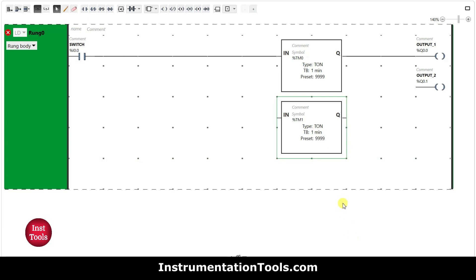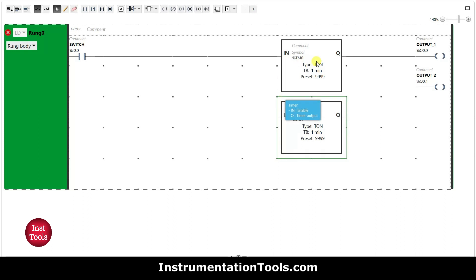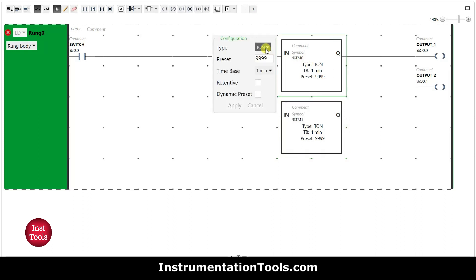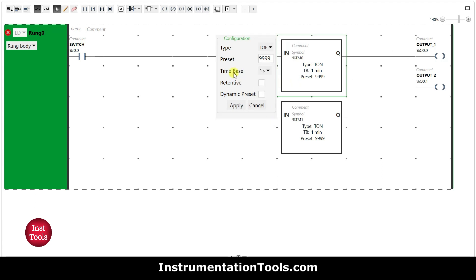Output 1 will be turned off after 10 seconds and output 2 will be turned off after 15 seconds. The preset values are 10 seconds and 15 seconds. The timer type should be T-OFF. For output 1, I will change the time base to seconds and set the preset value to 10, then click Apply.